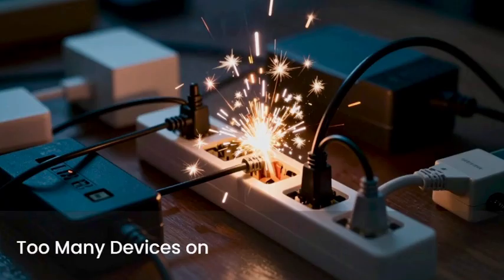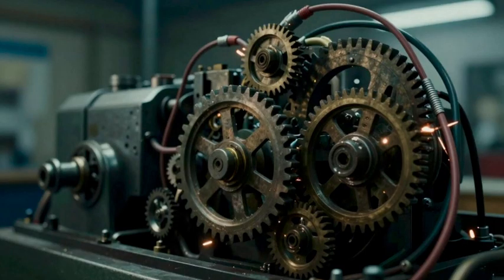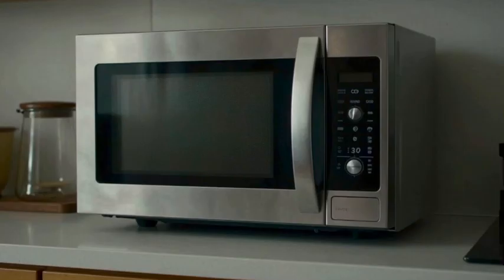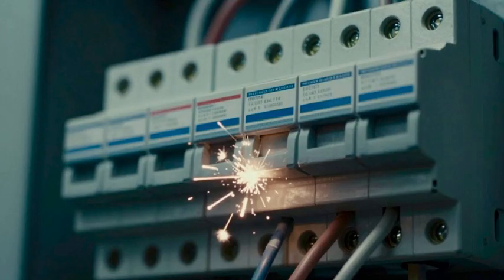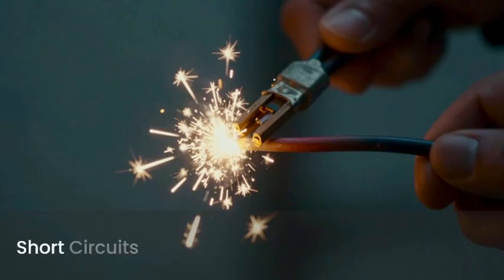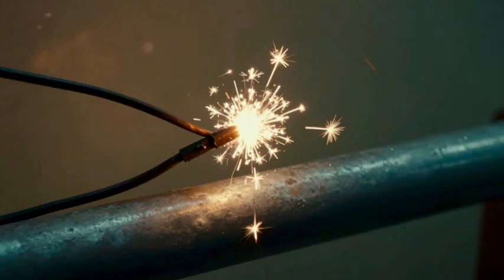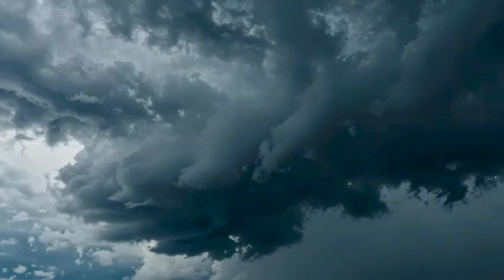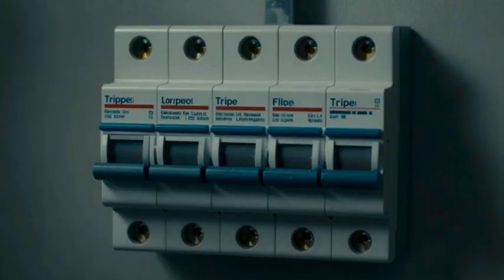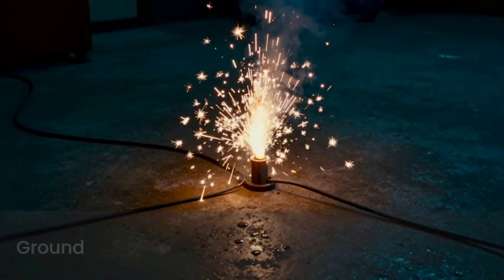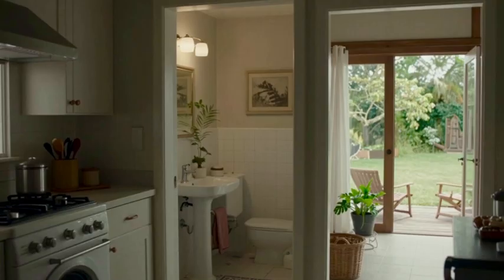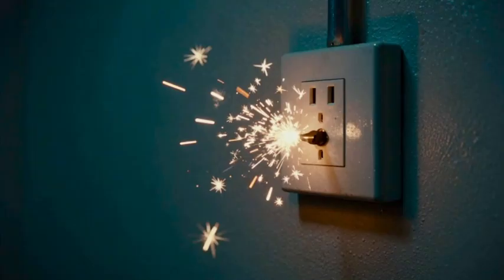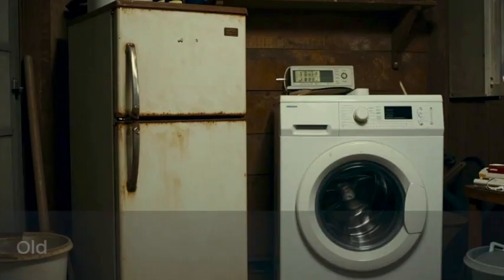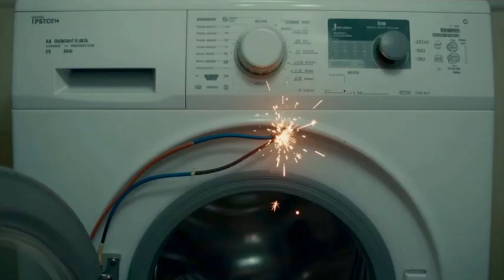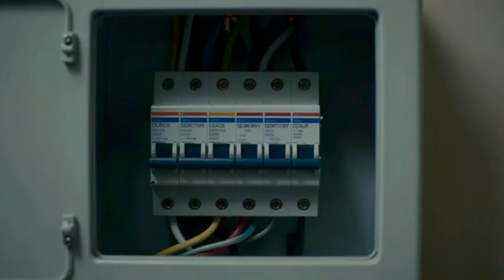Let's talk about the most common reasons this happens. Too many devices on one circuit. This is the most common cause. For example, a space heater, a microwave, and a gaming PC, all running on the same circuit, can overload it. Short circuits. This happens when a hot wire touches another wire or metal. It's more serious and often comes with a burning smell, sparks, or a breaker that immediately trips again. Ground faults, common in kitchens, bathrooms, or outdoors. Water and electricity don't mix, and breakers trip to prevent shock. Old or faulty appliances. An appliance with damaged wiring can cause repeated trips. Knowing why it tripped helps you decide whether it's safe to reset, or time to call for help.